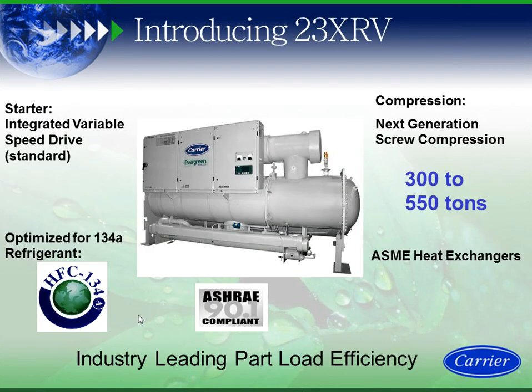Now we're going to talk a little bit about our 23XRV screw chiller. The variable speed 23XRV screw chiller, it says here 300 to 550 tons. Actually, I apologize. We just recently have a new compressor that came into the lineup on this machine, and it's from 250 to 550 tons. What we did here with it, because VFDs are so prevalent, we put a VFD standard on it. We optimized around 134A because that's the refrigerant that almost every major player has in the marketplace, and it has no phase-out date in the United States.